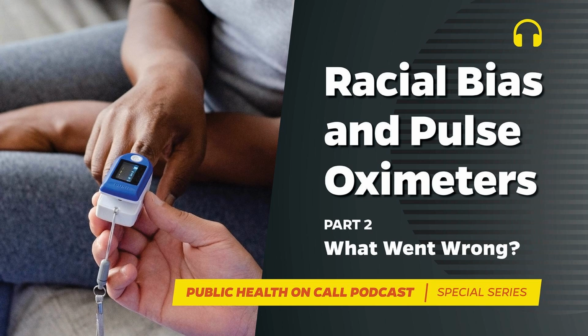In 1990 came one of the first studies to describe differences in pulse oximeter accuracy based on race. It found that pulse oximeters overestimated oxygen saturation to a greater degree in Black patients than in white patients. Then, in 2005 and again in 2007, more research emerged finding the same thing, that pulse oximeters overestimated arterial oxygen levels in individuals with darker skin tones.